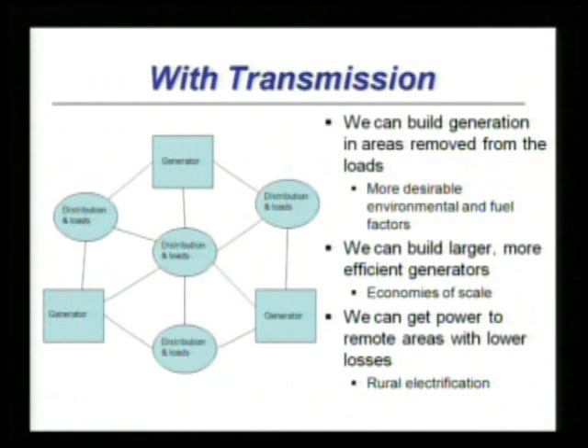With transmission, though, we can look at energy differently. Energy typically benefits from economies of scale, so to drive your cost per kW down in a generation facility, it makes sense to make it bigger. 1,000 megawatts of a certain technology is typically cheaper on a per kW basis than 500 megawatts of the same technology. The bigger the scale, the better off you are in terms of cost of energy. Doing that might require being in a more environmentally sensitive area, a less sensitive area, or an area closer to fuel resources, and to facilitate that, you need transmission.